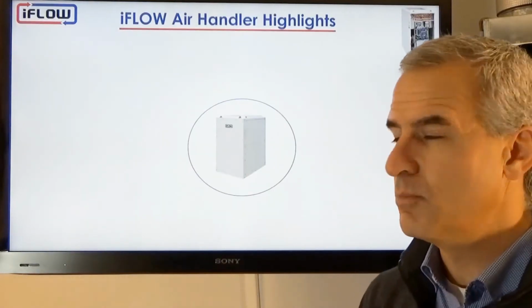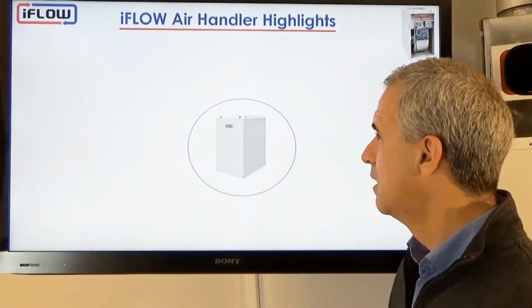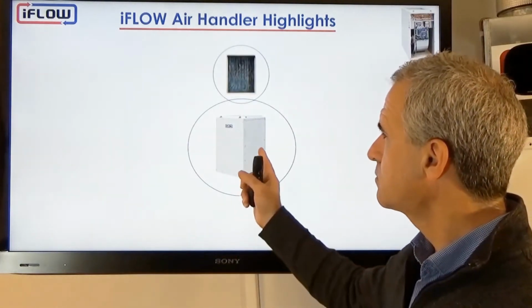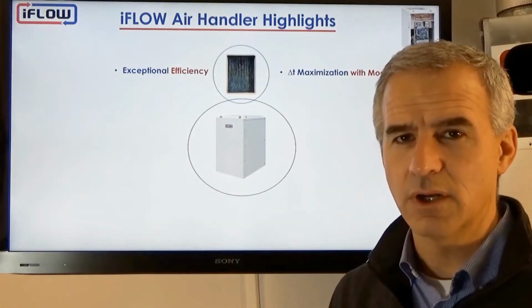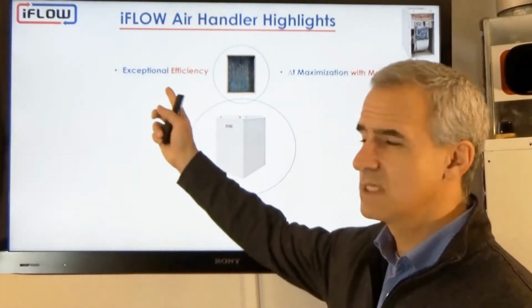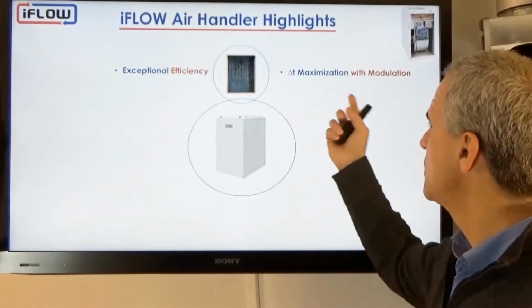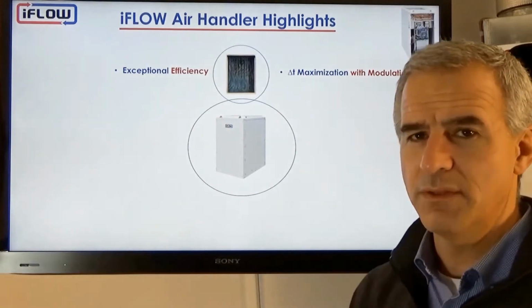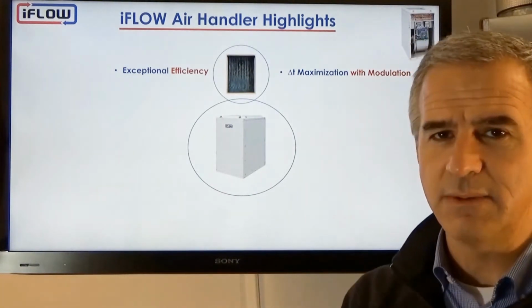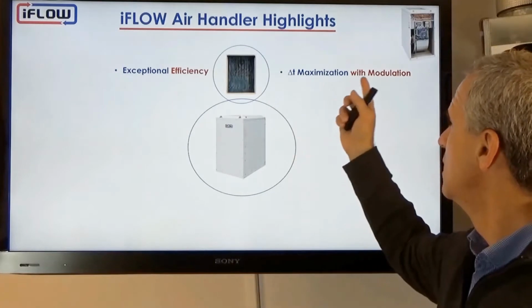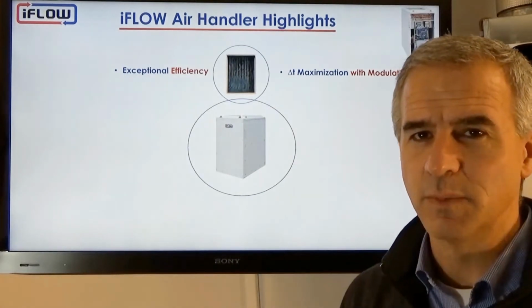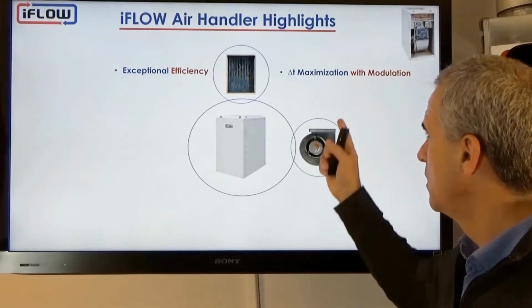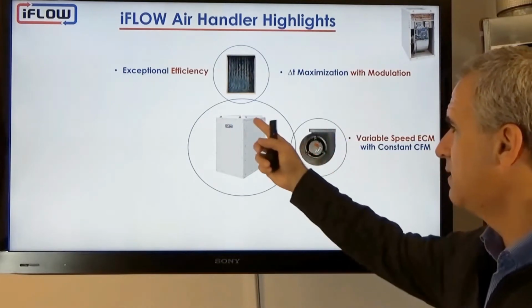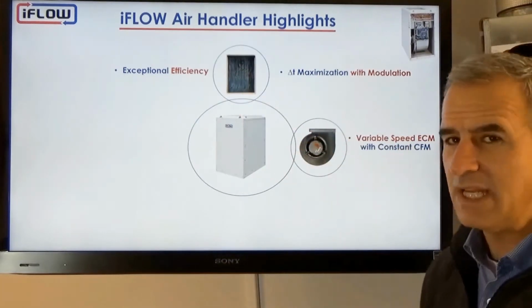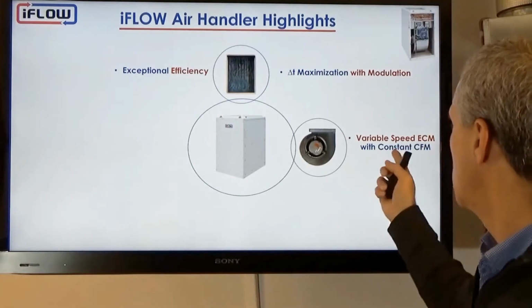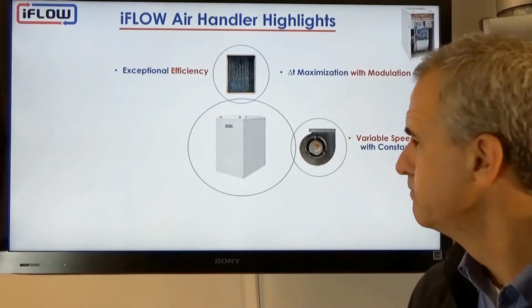So let's look at some of the components that make up the air handler. There are four main components. First and foremost, the hydronic coil. Our coil delivers exceptional efficiency in the high 90s range, and we pair that with our control strategy for delta T maximization across the coil and modulation to give you maximum efficiency.